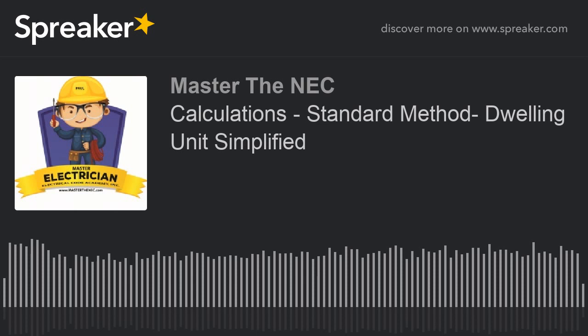34,701. So let's recap. Okay, the general lighting load was 6,150. The fixed appliances was 6,328. The clothes dryer was 5,000. The range was 8,000. The heat versus AC resulted in the AC. That was 7,613. Of the largest motor in the set that we're including in this calculation, it was the air conditioning compressor at 6,440 times 25%. That gave us 1,610 when we did the largest motor. And again, the air conditioning was 7,613. So we add those all up, and that's how we got the 34,701.